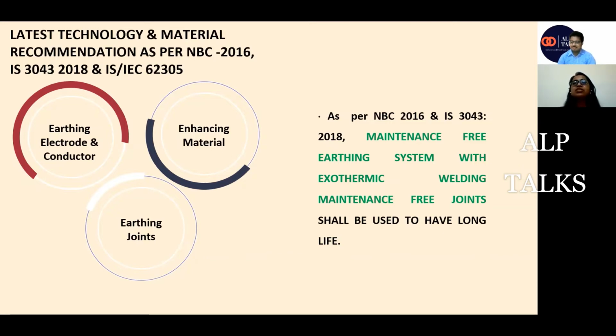So this happens because either we have done it with salt and charcoal, or if we have done chemical earthing, it is a bentonite based chemical. So it is very important what material we are using at the time of installation of the earthing system. It's clear. It will only maintain the earthing for a longer run. Now standards are also recommending maintenance-free systems, and the latest technology is also maintenance-free earthing, for every application, be it for metros, lightning systems, transformers, DG sets. For everything we can do maintenance-free earthing.